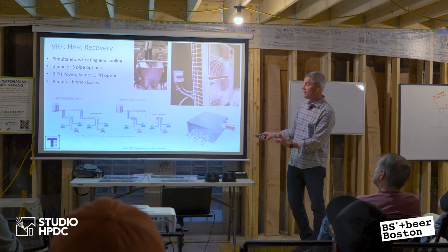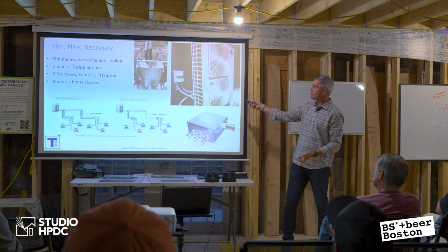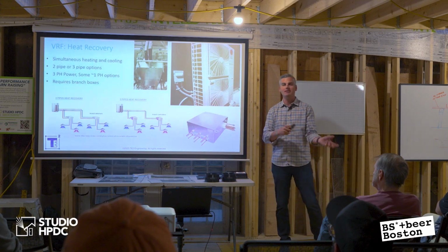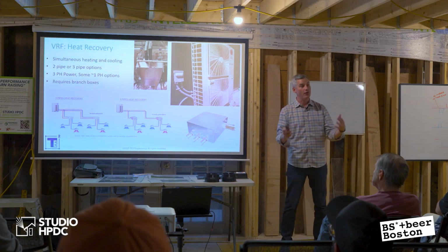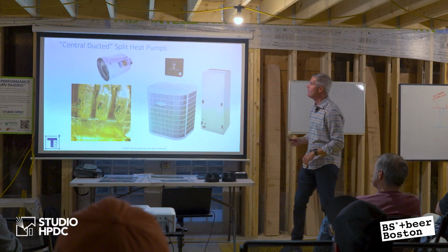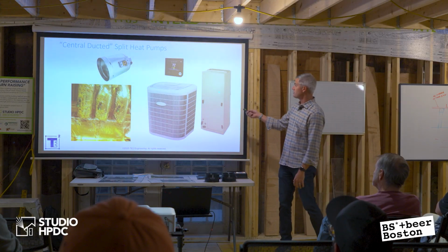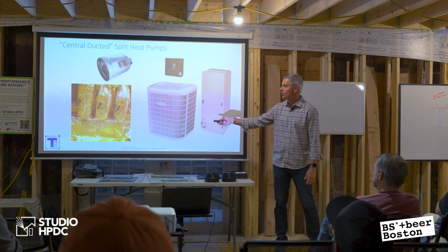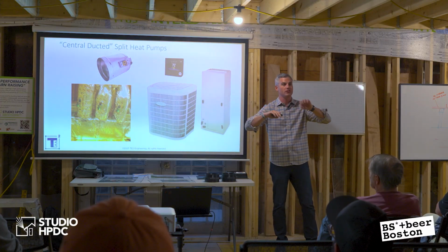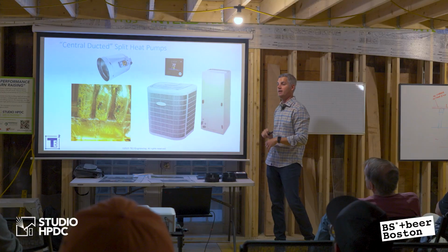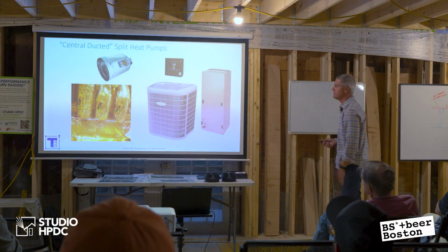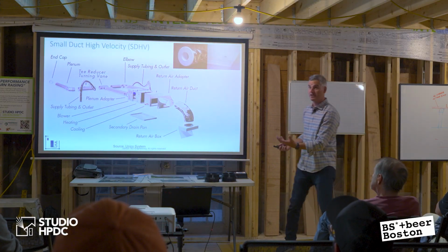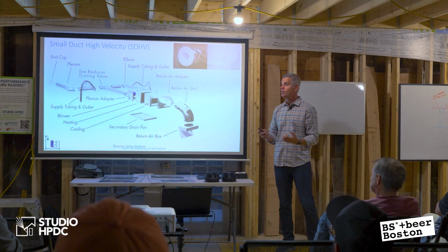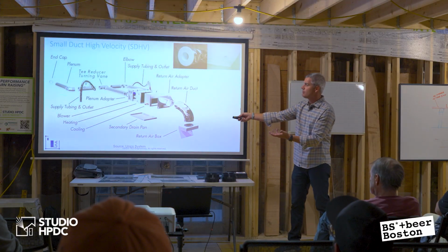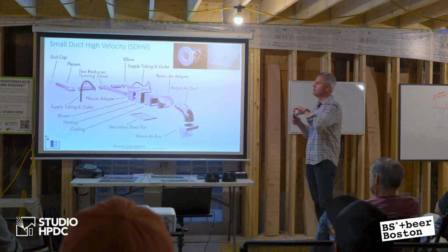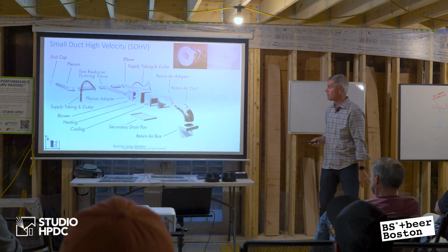You can go VRF heat recovery, right? Got bigger branch boxes, outdoor units, branch boxes. Now you can do simultaneous heating and cooling. That's another flavor of VRF, a different style. You also have central ducted heat pumps where I have an outdoor unit, an indoor unit, and I put some zone dampers on it. Those are gates that open and close to deliver air to a zone that needs it. That's a central ducted heat pump, a central split heat pump. You have small duct high velocity, another different tool in the toolkit. Pros and cons, but again, snaking small tubes at a very high pressure to send out really high jets of air, high velocity into the space.